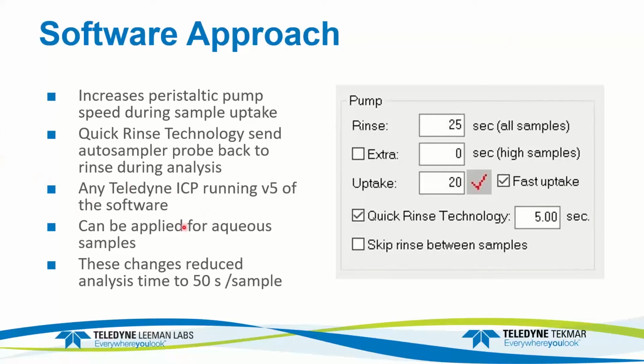Any Teledyne ICP that runs version 5 or later of this software can do this. It can be applied for aqueous samples. We've done this with, say, soil samples for high-speed analysis of soil samples. We also have the ability to skip the rinse, which we don't do because of the differences in the wear metal samples, which could be high concentration or low concentration. But in some soil samples where everything is relatively the same concentration, we can even skip the rinse, increasing the speed even more. So by doing all these changes, we were able to reduce the time to under a minute, comfortably at 50 seconds a sample.